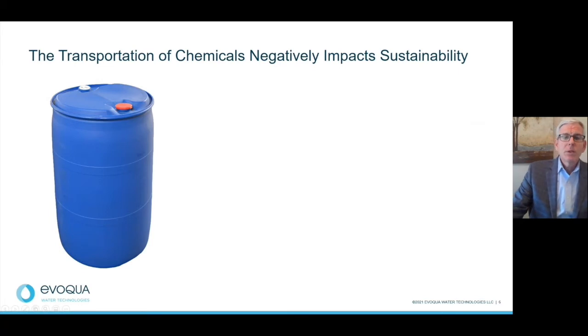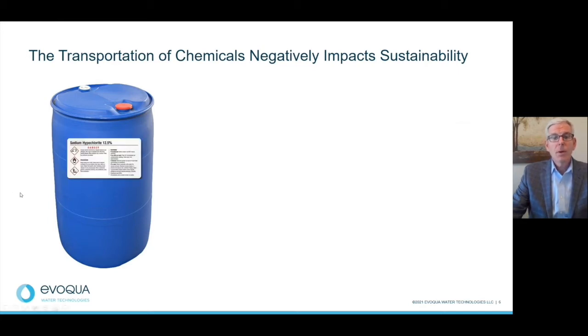Liquid-based chemical formulations are often made with a low percentage of active ingredients. The main reason for this is because as the active ingredients become more concentrated in a liquid formulation, they become unstable. I'd like to highlight one of the more common chemicals used to disinfect cooling water, which is sodium hypochlorite, otherwise known as bleach.